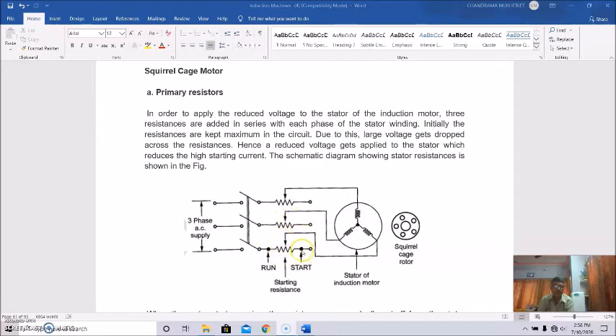So these are the series resistors connected with this phase, this is connected with this phase, and this one is connected with this phase. If it is A, B, C, these are connected in series with the stator winding. Initially the resistance is kept at maximum. That is, the start position, the total resistance is inserted in the windings, and as a result the required voltage drop happens across the starting resistance, and the reduced voltage is impressed on the stator winding. Gradually this rheostat resistance is decreased, and finally it is cut off to get the full voltage applied across the stator winding. Hence a reduced voltage gets applied to the stator, which reduces the high starting current.